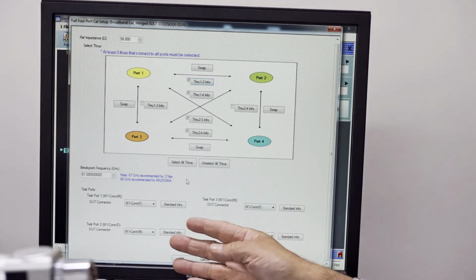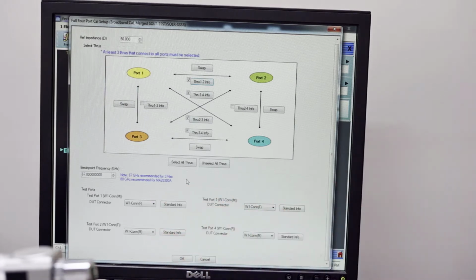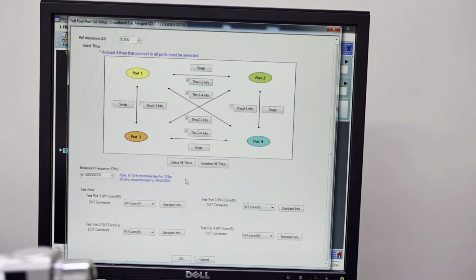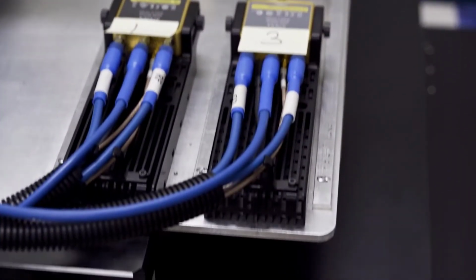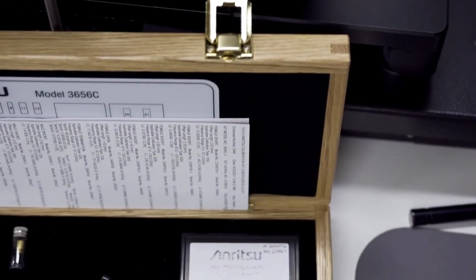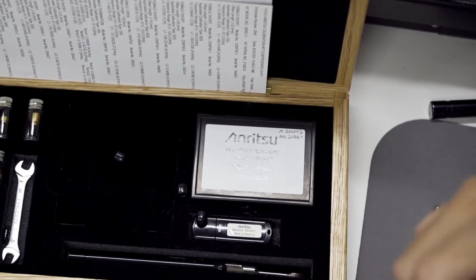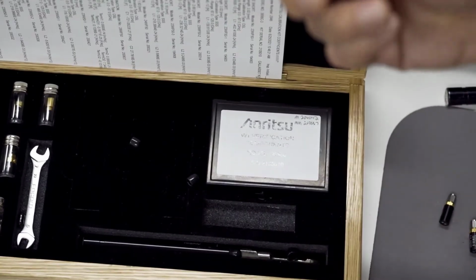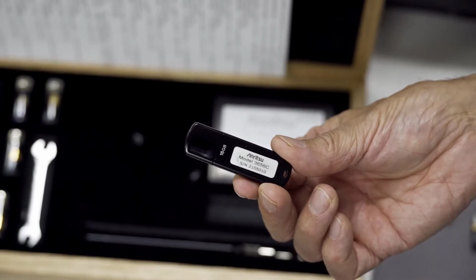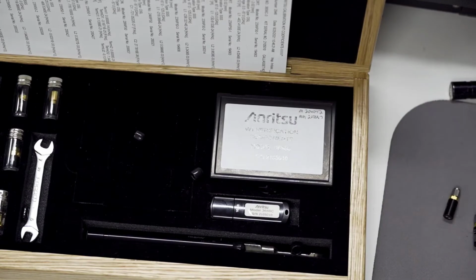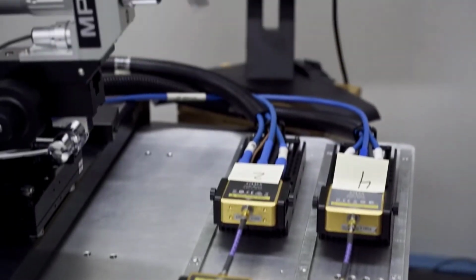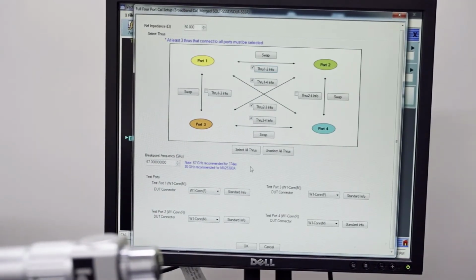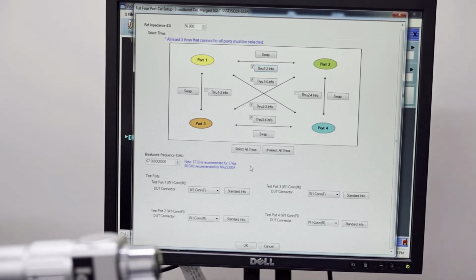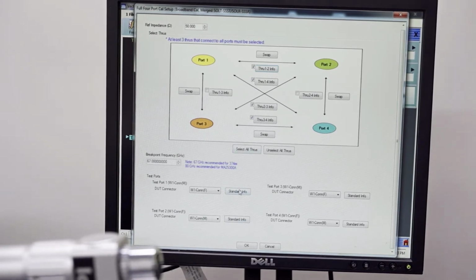Okay? And so next then is we define the test ports. Okay, so in this case, if you recall the test set that I was showing, we have calibration standard coefficients. And you can see that in the cal kit, we have this USB drive that provides the calibration coefficients for these standards. And so we load that into our VNA, and then we point our standard information to that.